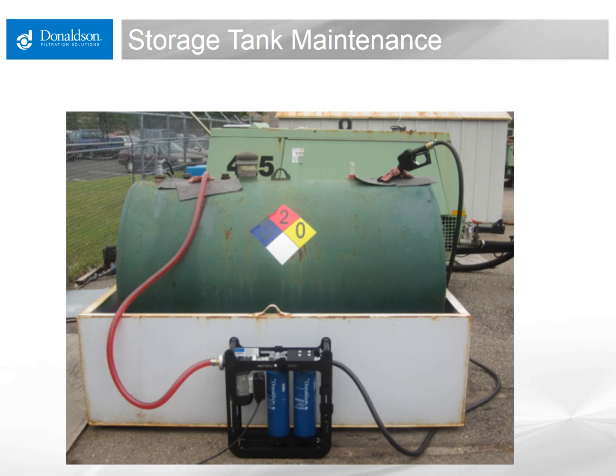In this case, a hose that is put down at the bottom of the tank on the low end can get some moisture out of there, and you can perhaps collect it in an absorber filter in this circulation system and get that fuel clean and dry prior to winter. If that water has frozen in the bottom of the tank, that's probably going to have to stay there until things warm up. If you're operating a system that has a pump draining near the bottom, you do not want that water building up, or it's likely to plug the pickup from your tank, whether it's a stationary tank or a mobile tank. If the fuel pickup is near the bottom and you have a significant amount of water there, you can freeze ice on that pickup, and you will not be able to get that going until you can thaw that out.